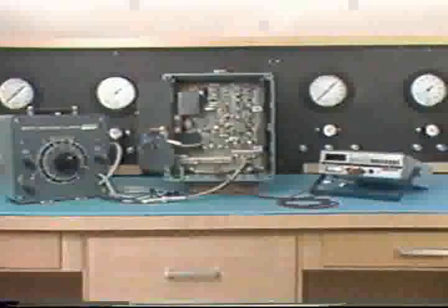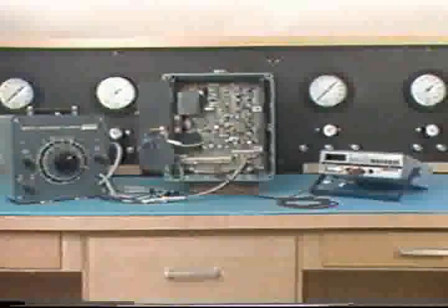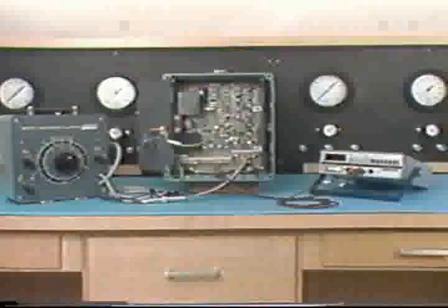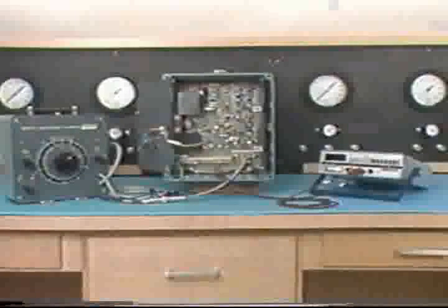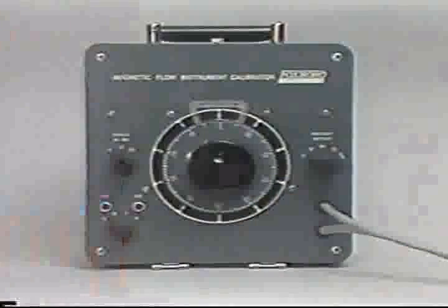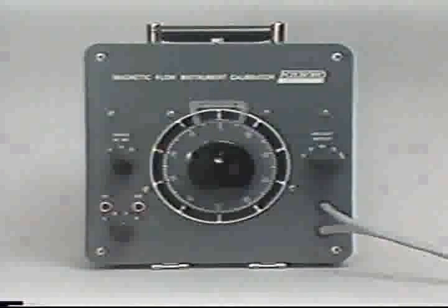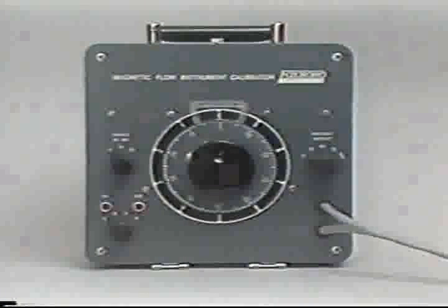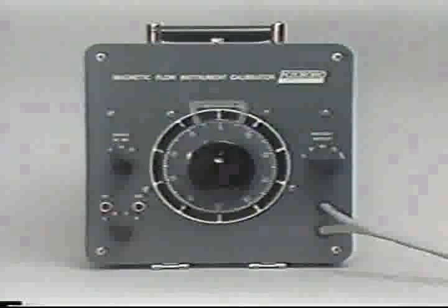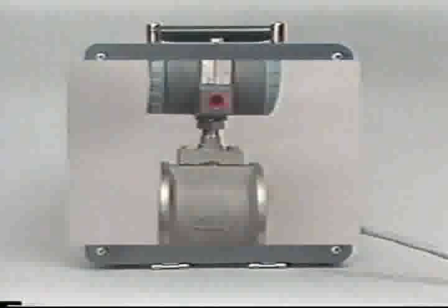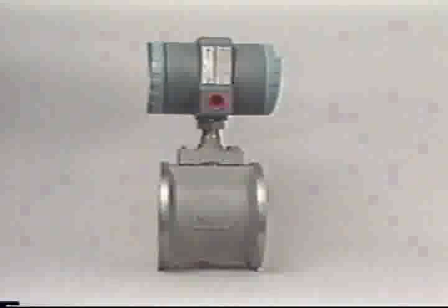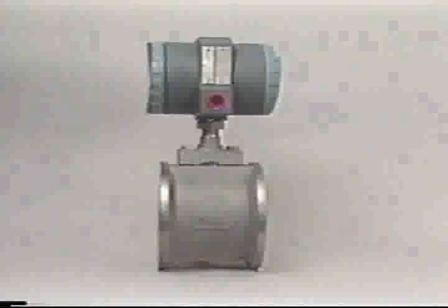We've seen that to calibrate a magnetic flow meter, you not only must use the appropriate test equipment, but also properly set the magnetic flow meter calibrator. On a magnetic flow meter calibrator, you can set the input signal, maximum output signal, and the test points used in calibration. In the next segment, we'll look at another type of flow meter and the procedure for calibrating it. But for now, stop the tape to review what you've seen.